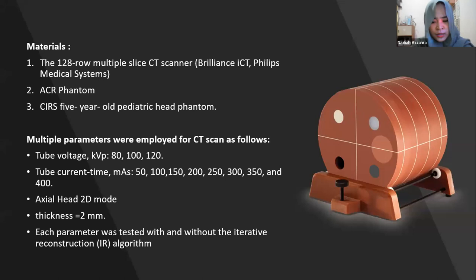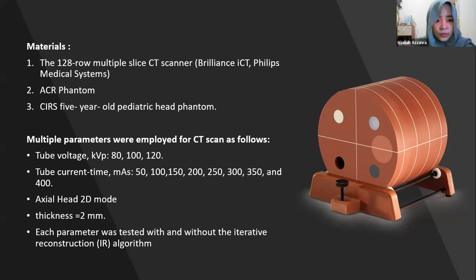The first material is a 128-slice CT scanner. The second is a ACR Phantom, and the third is a five-year-old pediatric head phantom. The CT scan parameters applied are: tube voltage (kVp) at 80, 100, and 120; tube current-time product (mAs) from 50 to 400. The CT scan is operated in axial head 2D mode with a slice thickness of 2 millimeters. For each parameter, tests will be conducted with and without the iterative reconstruction (IR) algorithm.